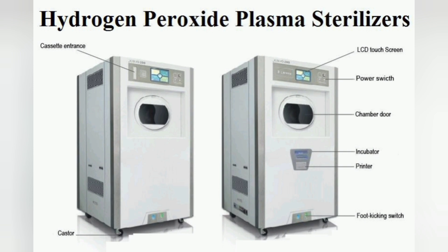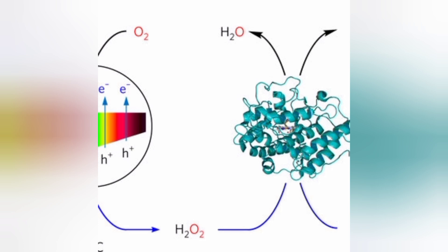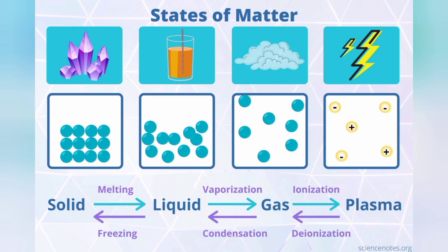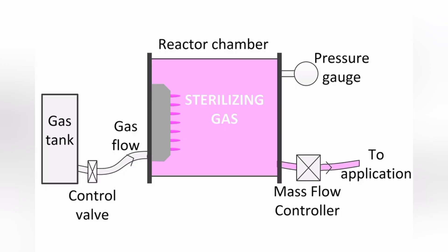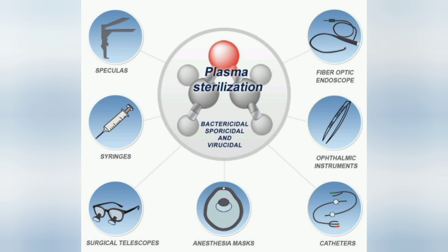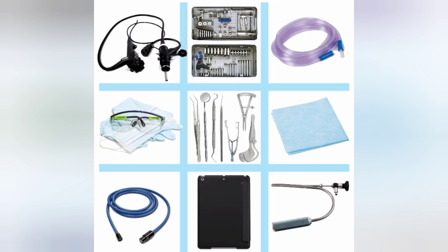The third type is hydrogen peroxide plasma sterilization. In this method, hydrogen peroxide (H2O2) is activated to create a reactive plasma or vapor. Plasma is the fourth state of matter, distinguishable from solid, liquid, and gas, and is produced through the application of a strong electromagnetic field. The cloud of plasma consists of ions, electrons, and neutral atomic particles that produce a visible glow. Free radicals of H2O2 in the cloud interact with membranes, killing any enzymes or microorganisms. Materials and devices that cannot sustain heat or moisture are sterilized by plasma sterilization.